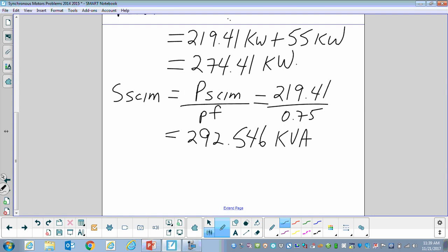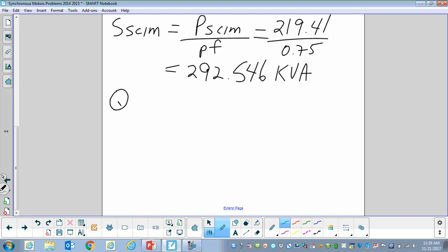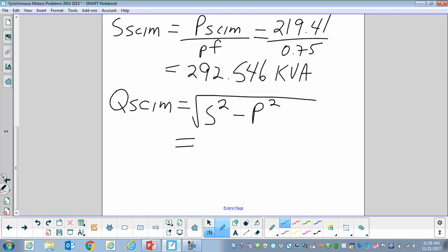While we're doing squirrel cage, the last variable to figure out is Q of the squirrel cage induction motor. We can use the Pythagorean theorem: the square root of S squared minus P squared, again for the squirrel cage induction motor. Plugging those numbers in, we get 193.5 kVARs. This is an important number because it will also appear in the existing plant calculations.